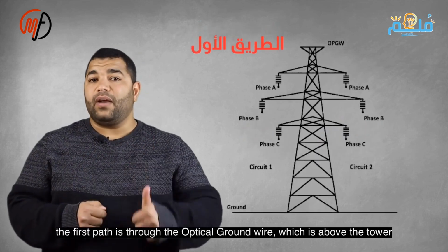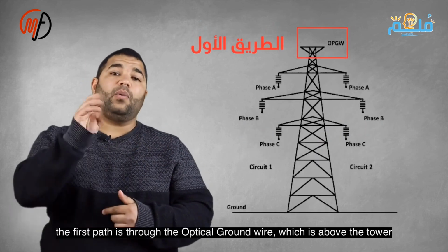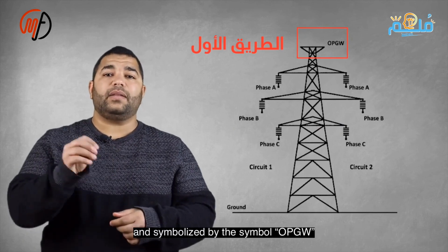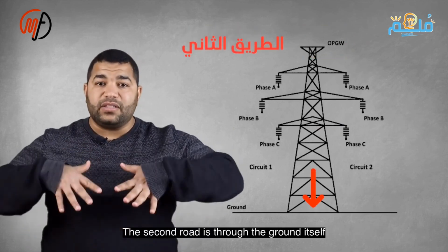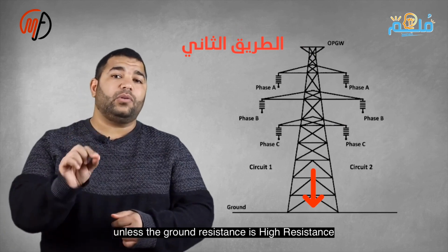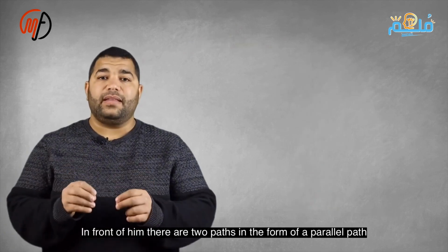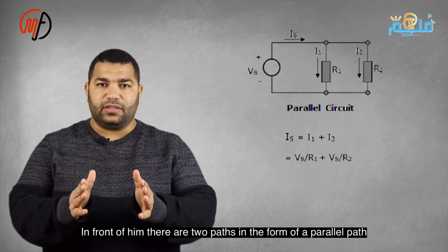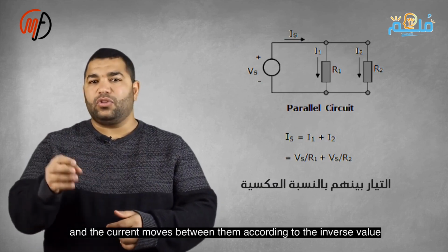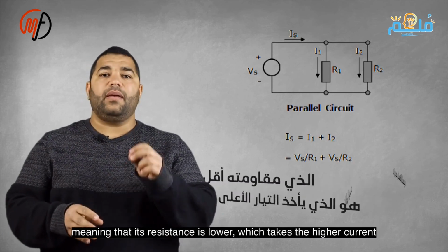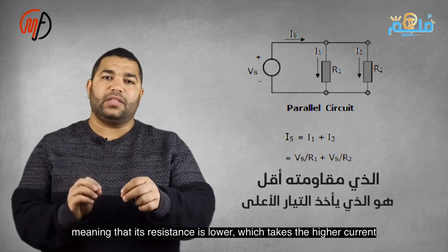The first path is via the optical ground wire, OPGW, at the tower's top. The second path is through the ground unless high resistance requires a parallel setup. Current flows inversely proportional to resistance values, with lower resistance taking more current. Ground faults in transmission stations are more dangerous than in generation stations.